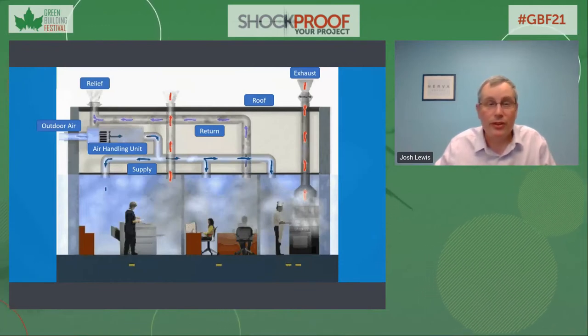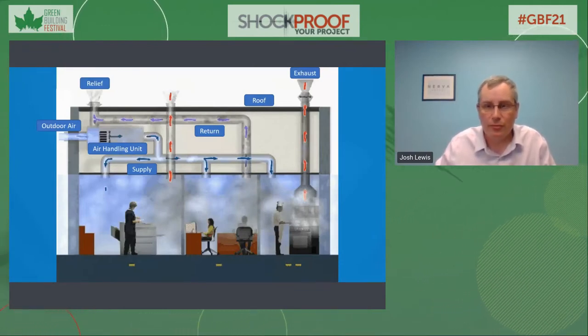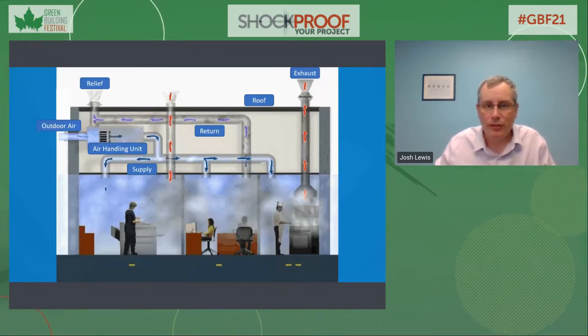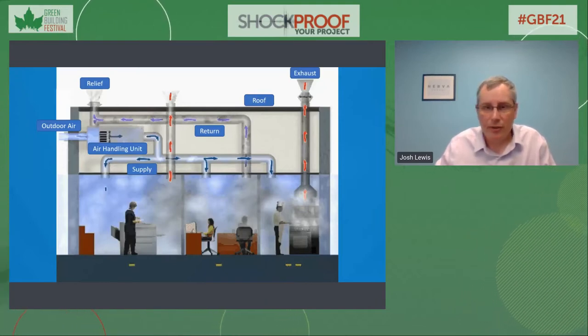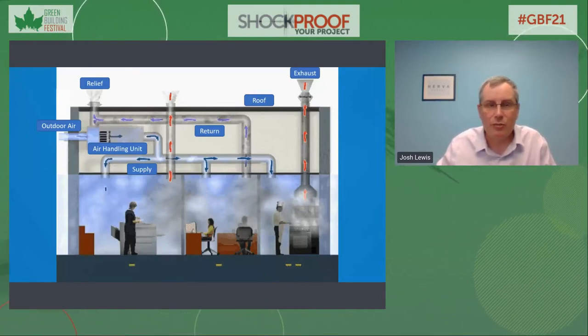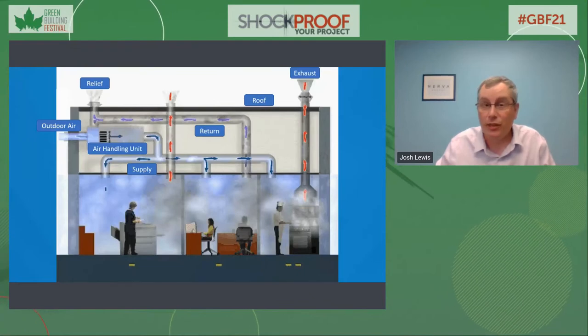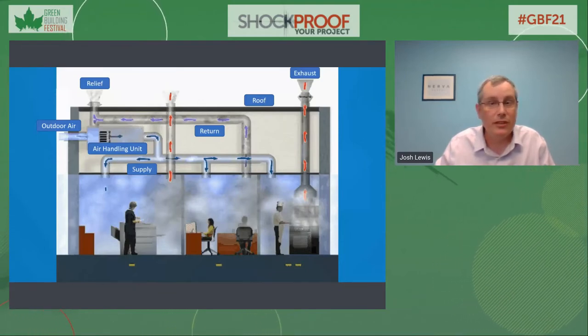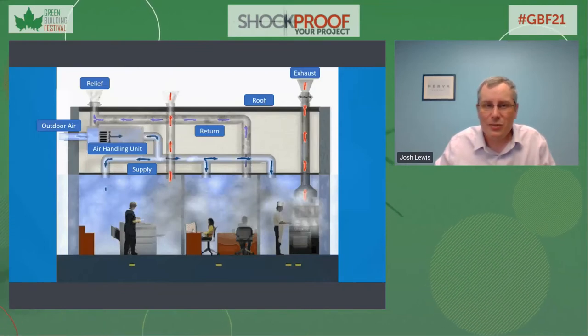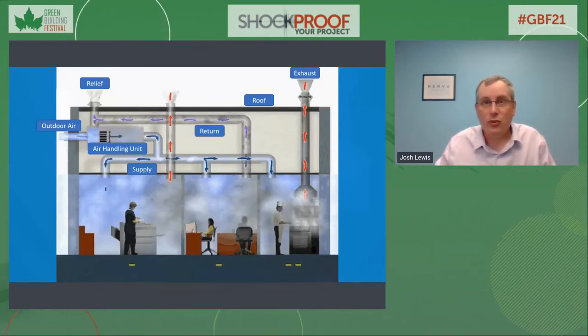Dilution can be further broken down into two major strategies: keep air moving and the introduction of fresh air into the building. Let's start with keep air moving. So keeping air moving through buildings is key for a healthy environment. Stale, stagnant air can expose the occupants of a building to several risks, including both airborne contaminants of all kinds, high CO2 levels due to the breathing process of people within the space, and also odors that act as irritants. And as discussed previously, good air circulation is critical for filters to perform properly.